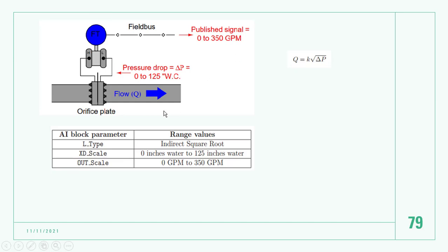This one is a flow transmitter, a different pressure flow transmitter. It's an indirect square root. This flow formulation is Q is flow equal K is constant, square root delta P, where delta P is the different pressure transmitter. This pressure minus this pressure equal delta P. Okay. This one XD L type indirect square root. XD scale here from 0 to 125 inches of water, out scale is 0 GPM. This flow. Okay.